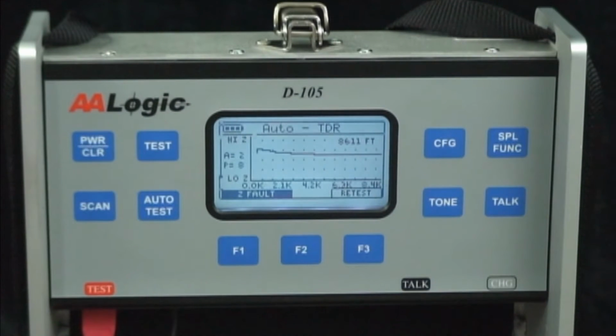In this case, it's gone through a balance test. It's also done a noise test, and it has an auto TDR looking for the distance. And here we can see under the TDR that we have some faults, an impedance fault, and we can see that it's 8,611 feet according to the TDR. When the auto test is completed, the test can be restarted by pressing the F3 key. Normally what would happen is the user would switch to a new pair, hit the retest, and automatically go through the test cycle to test the next pair.